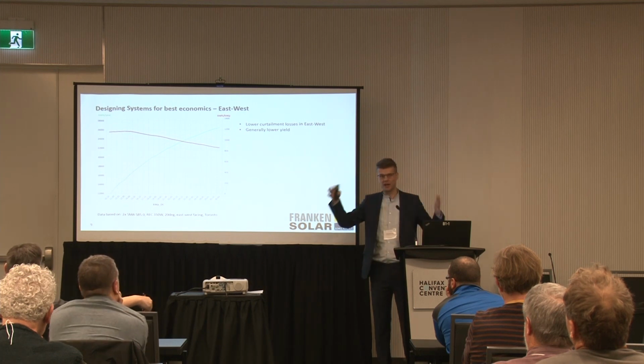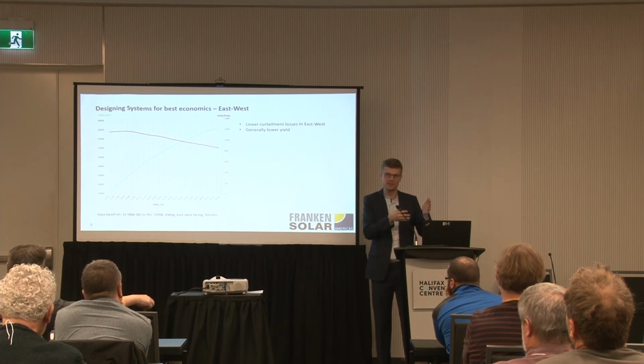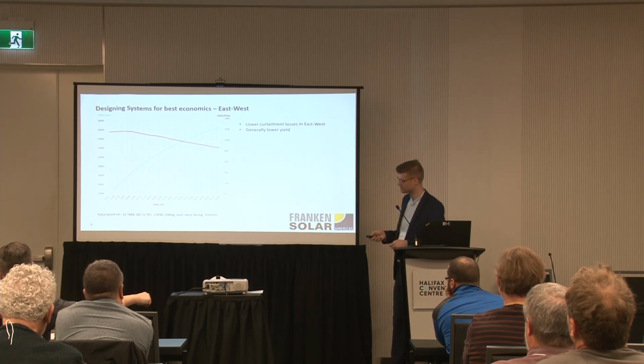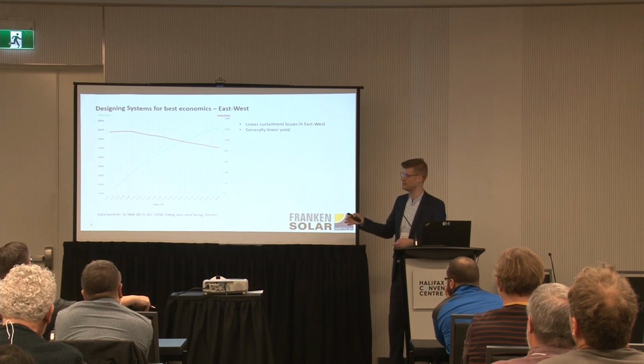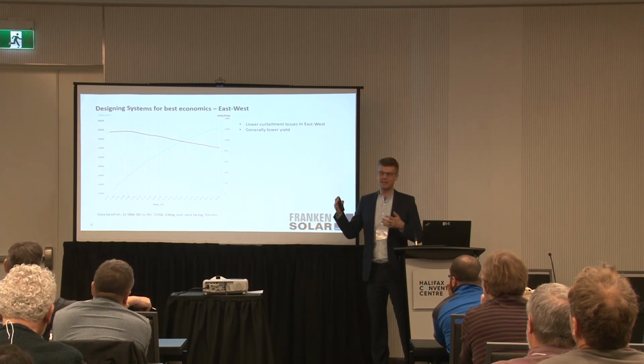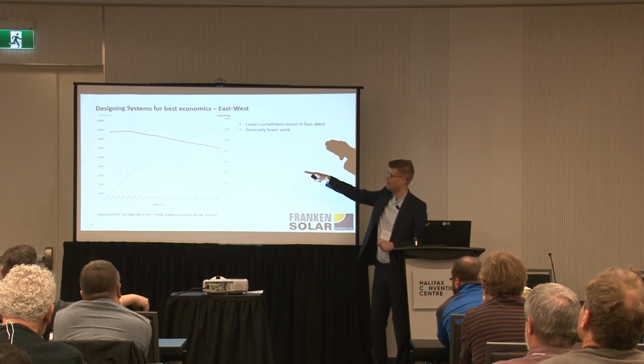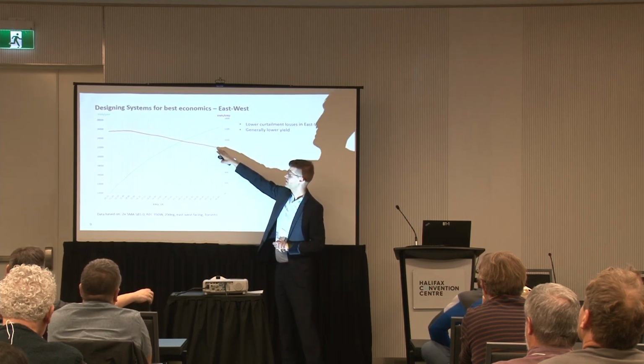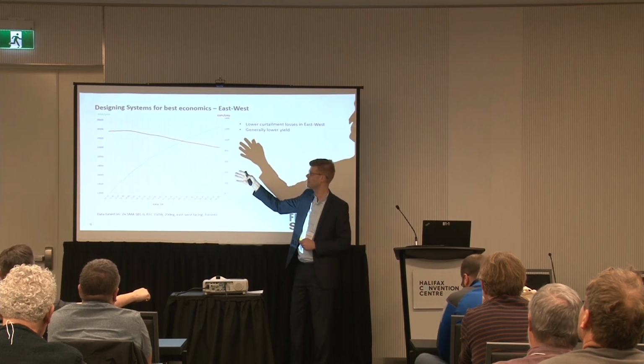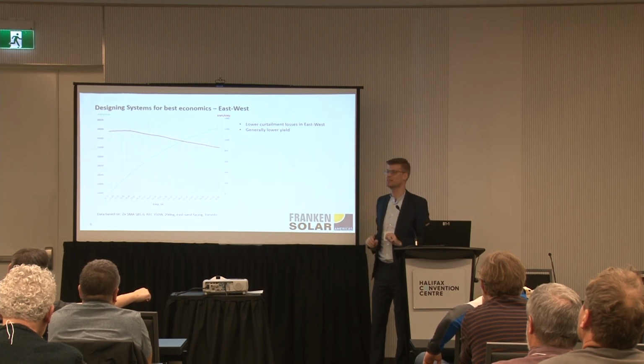And if we look at the entire curve over the day, it's a lot more smooth and doesn't have as high of a peak around noon because we have earlier production in the morning and later production in the later afternoon. And one thing we see right away, again, the red curve is our efficiency. And you see a little bit in light gray behind, that's the graph we had before from a south-facing only. And the first analysis is east-west facing system is producing less than a south-facing. Totally obvious. So the curve starts already a little bit lower. The other thing you can see if you compare these two graphs is that the decline in the production and the efficiency on the red curve versus the decline on the gray curve behind from the south-facing system is actually less severe based on the effect that I have these two curves separated by time of day.